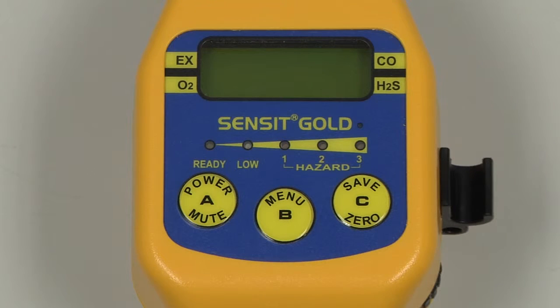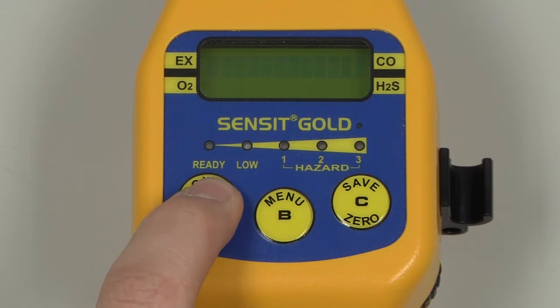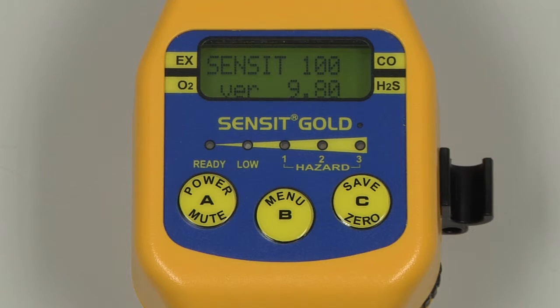To begin, power on the instrument by pressing and holding the A button. The model type and version number will be displayed, followed by a system check. The date and time will be displayed, along with the gas type, the serial number, and then the warm-up will begin. After the warm-up, the instrument will auto-zero and advance to the working display. Allow the instrument to warm up an additional 5 minutes before calibrating.